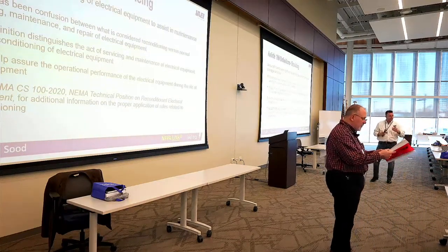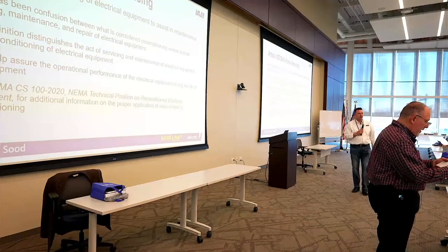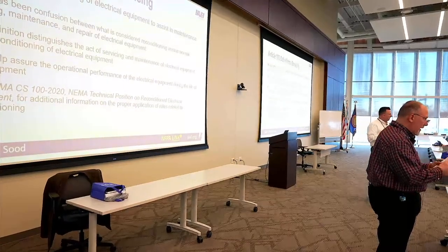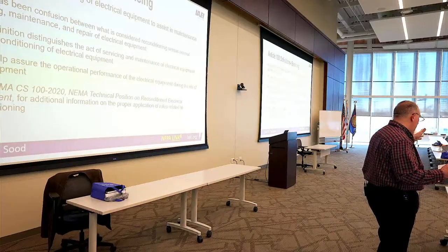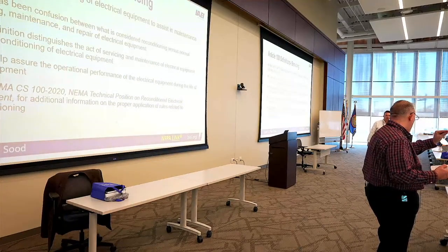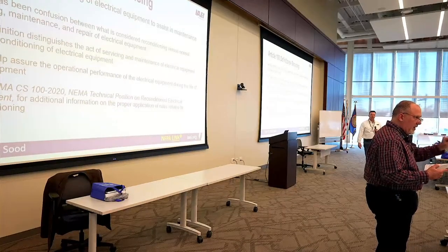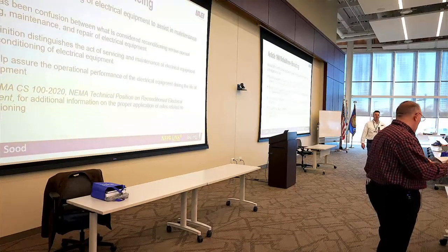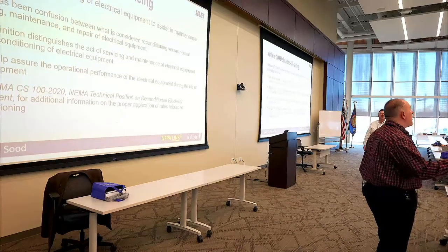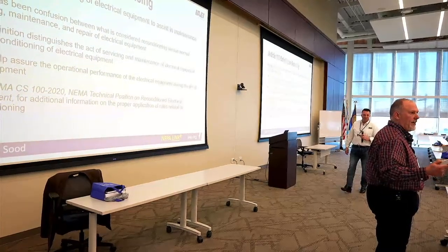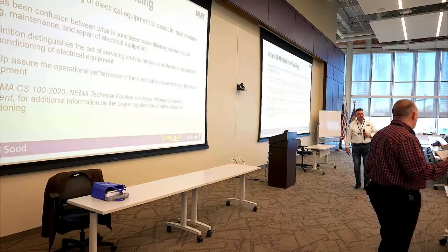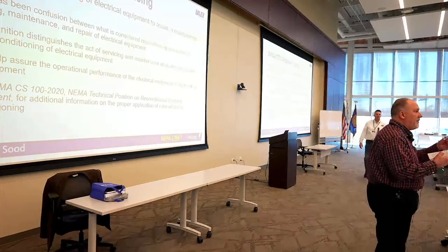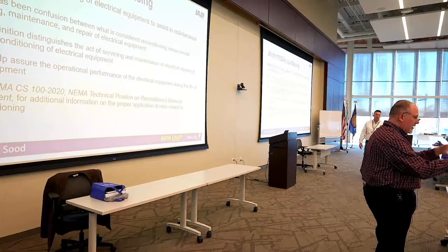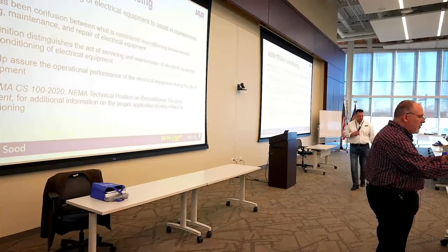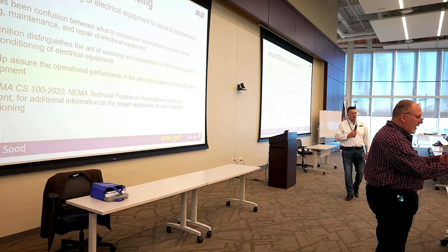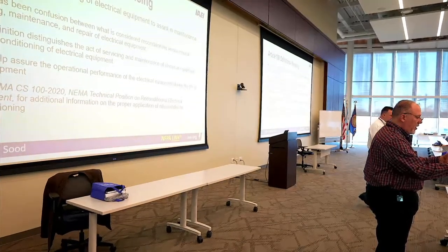So reconditioning is, pretty broadly, electromechanical systems, equipment, apparatus, or components that are restored to operating condition. So I have a panel board, and my breaker goes bad, and I'm going to replace that breaker. Am I reconditioning the panel board because it was broke and now I'm bringing it back to working condition? The code may say you're not permitted to recondition a panel board, right? So what am I doing? We had to add clarity: if I'm following manufacturer's instructions—look at the rest of the reconditioning definition—this process differs from normal servicing of equipment that remains within a facility, or replacement of listed equipment on a one-to-one basis.